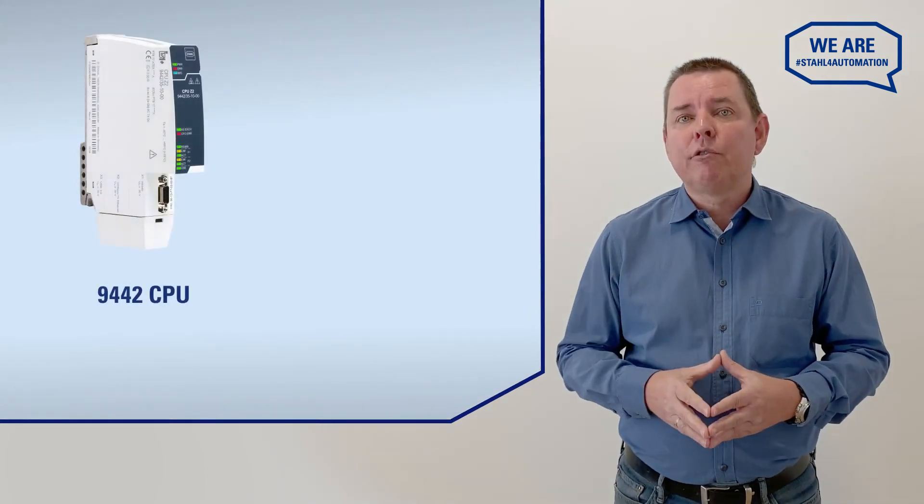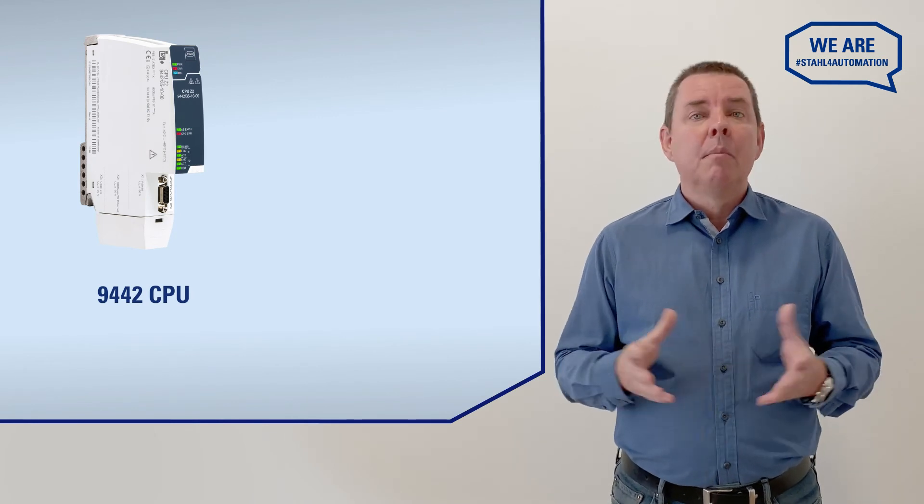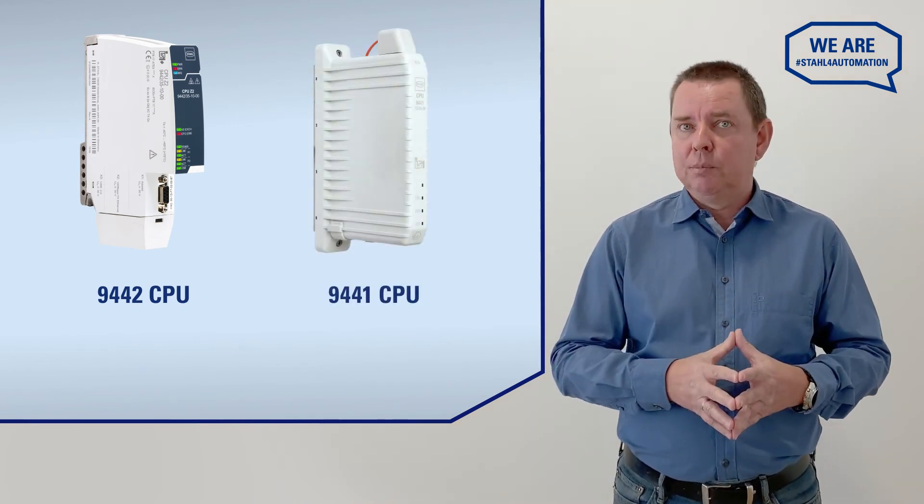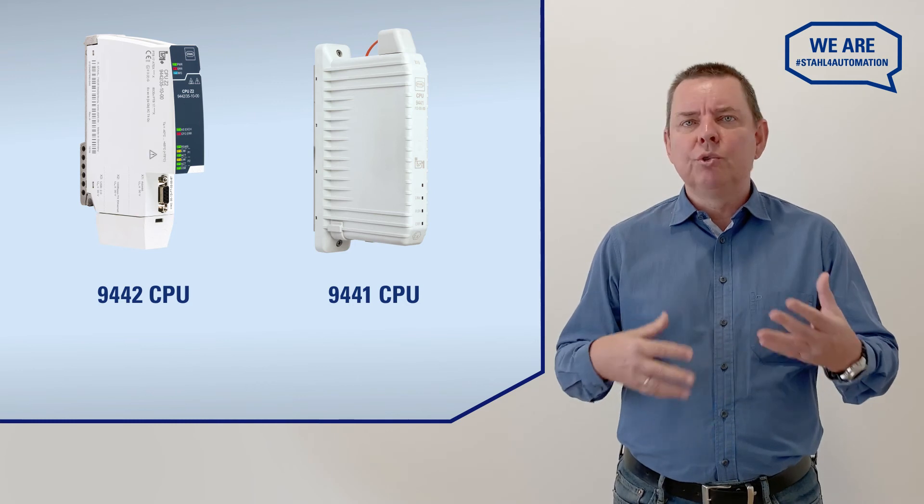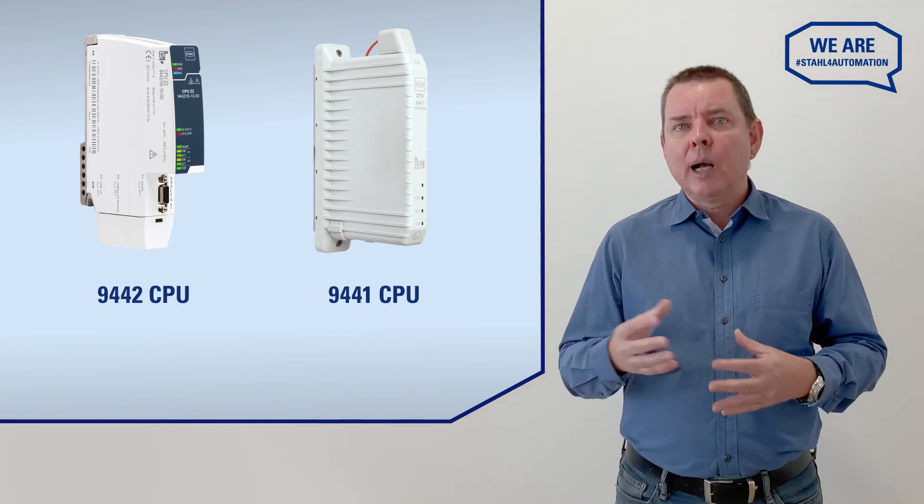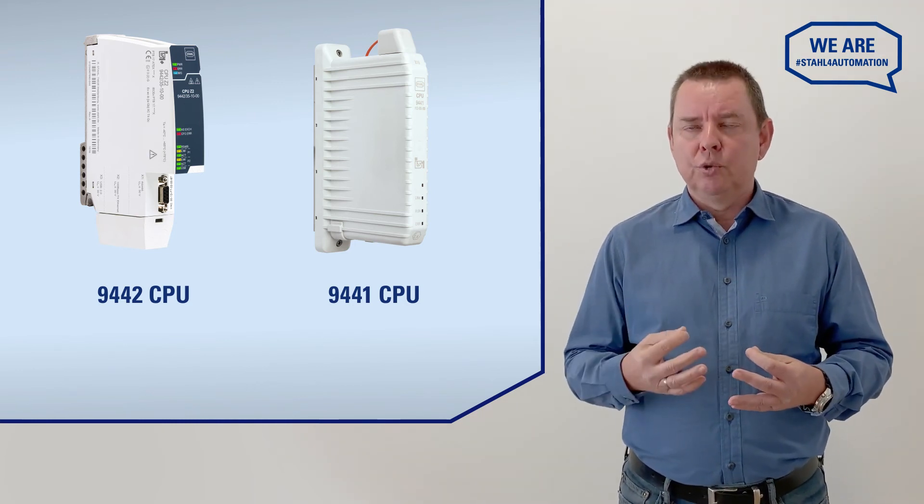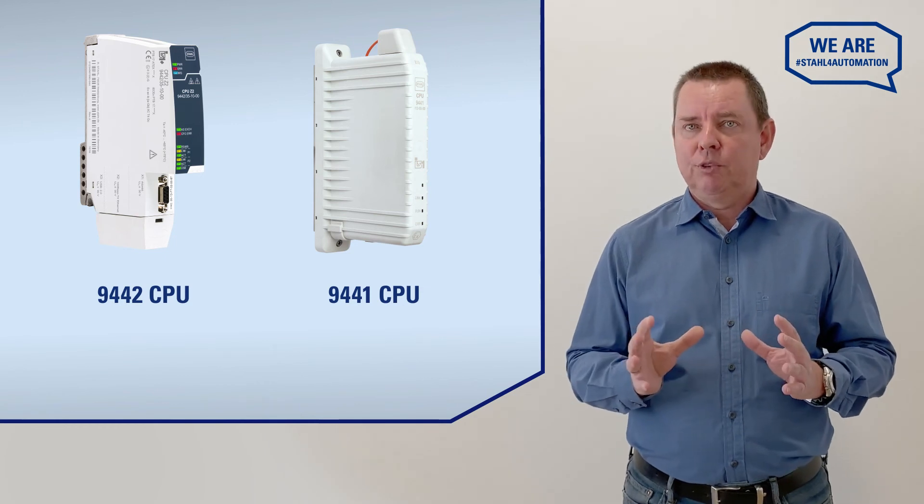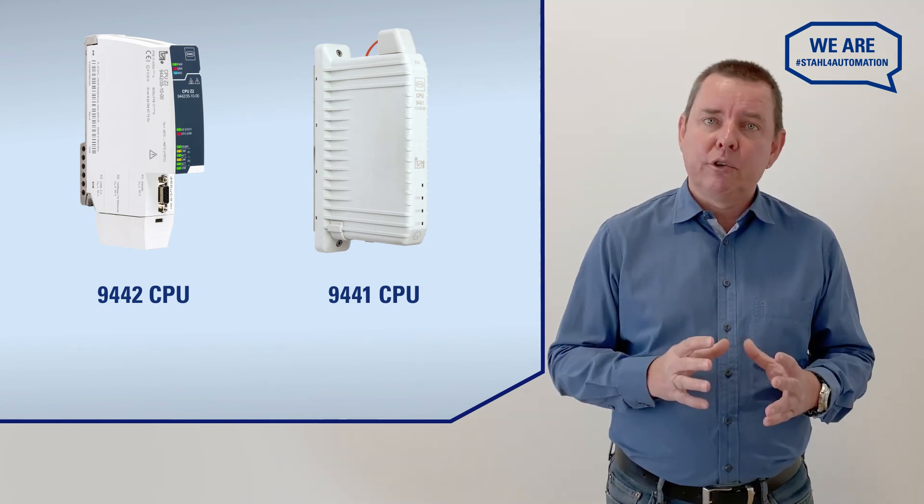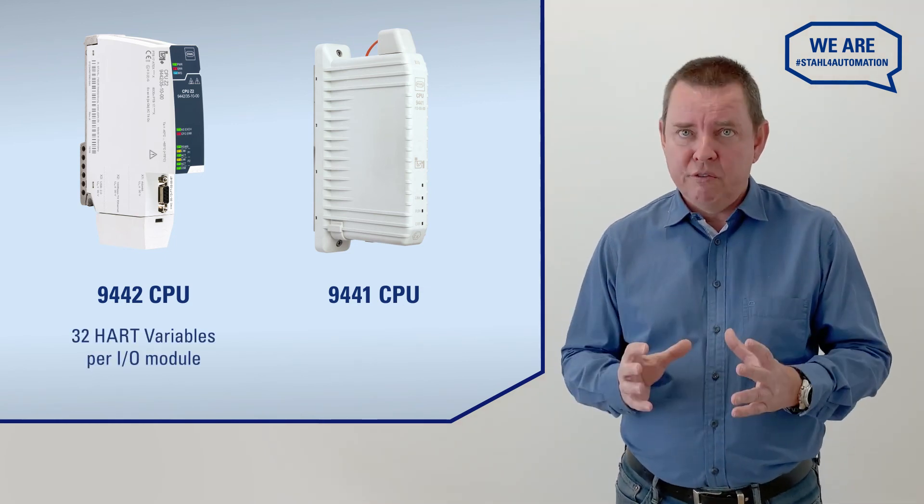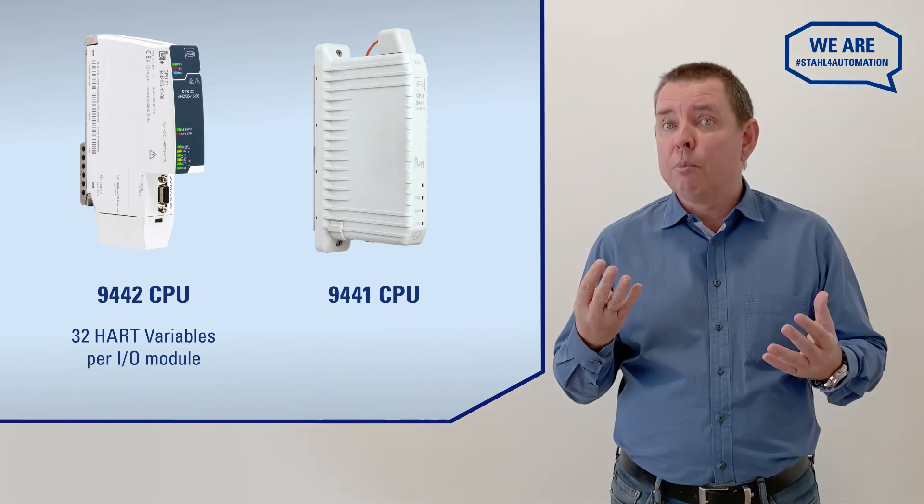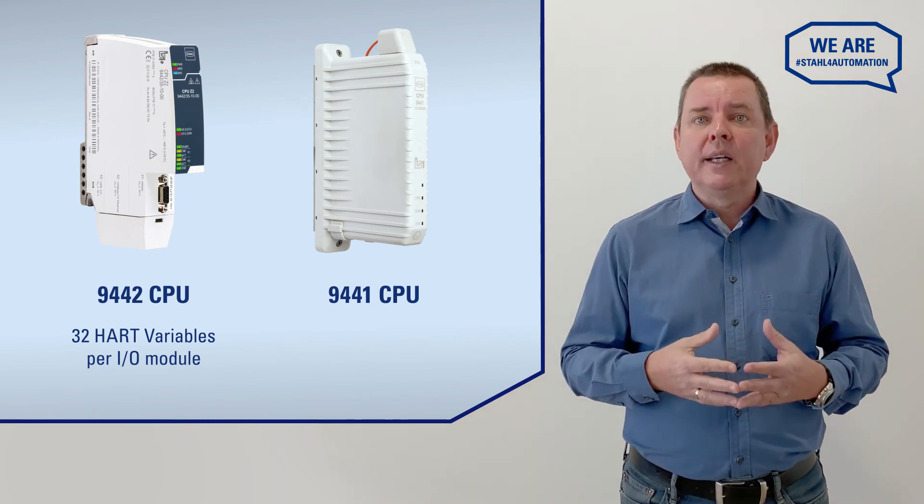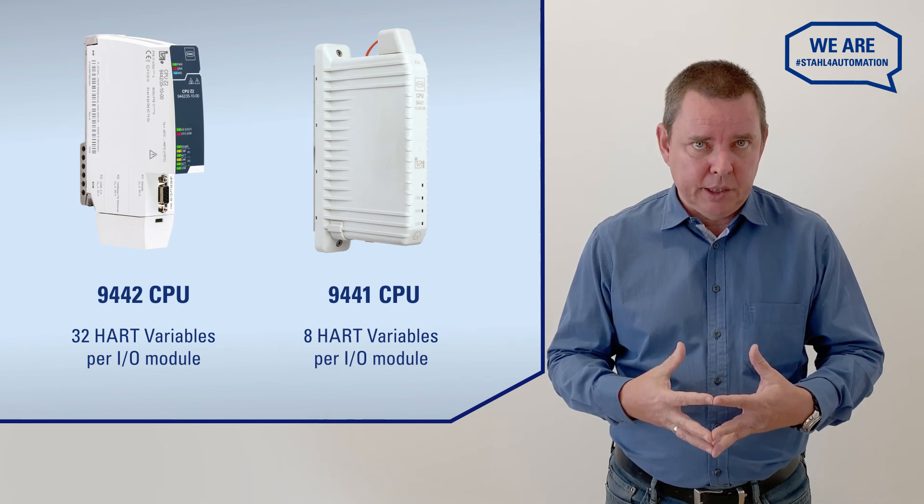We've used a 9442 CPU in our example, but you can tie 9441 CPUs into Rockwell by simply using the same process. When it comes to reading out your IO modules, the only major difference between them is that 9442 uses 32 variables for HART, that is 4 per loop, while 9441 can only map 8 HART variables.